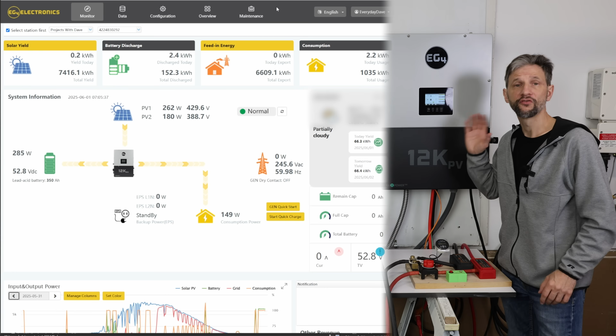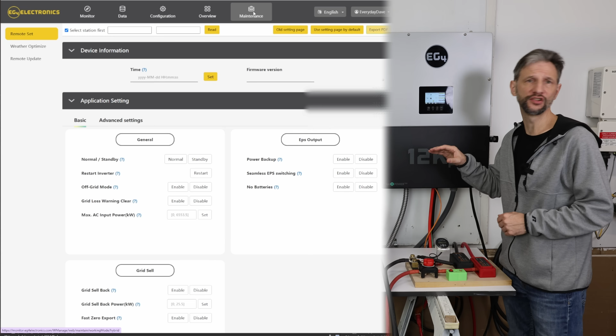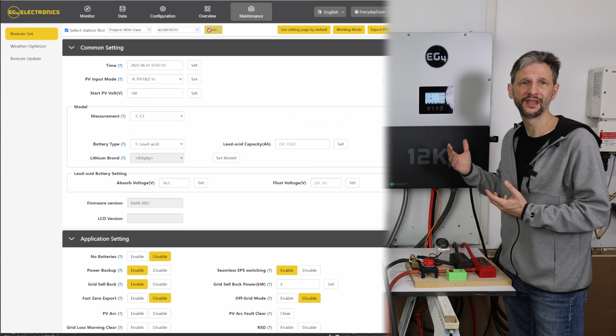This system does have the ability for communication depending on which batteries you're using. We're just going to use the manual mode to manage this battery. From the monitor page, I click on maintenance, then I use the old setting page and click on read to bring in the current values. If I were installing a battery with established communication, I would select lithium and the corresponding communication protocol.